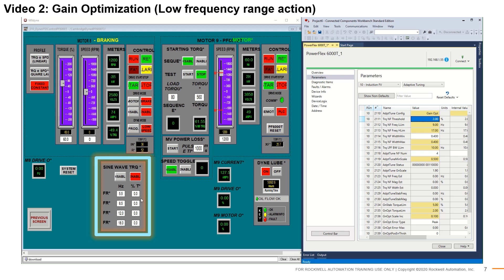Now let's start injecting a sine wave load at a periodicity below the frequency load limit. This simulates low frequency oscillatory behavior, which is a common indicator of a system operating in marginal stability. To resolve this, we wish to reduce the effective system bandwidth. It is observed that the gain scalar starts to drop. As long as the marginal stability condition persists, the gain will be continuously lowered. Once the gain scalar load limit is reached, adaptive tuning will no longer detune the regulator gains.